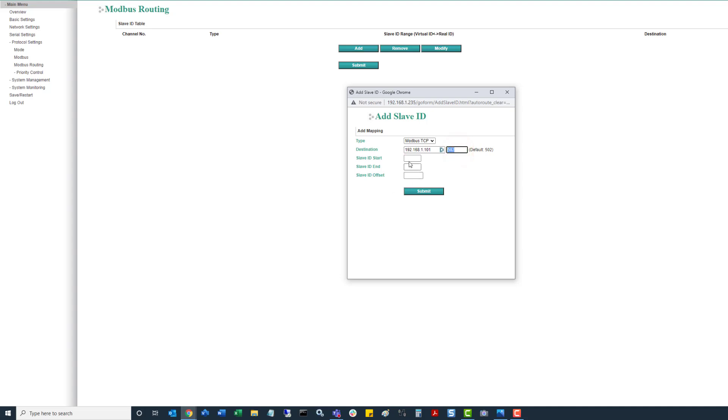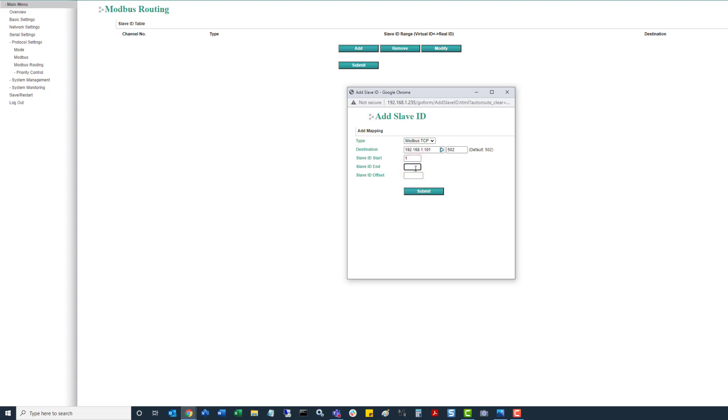So we have a start ID, end ID, and then there's an offset. So on this first one in this example, we're going to be using slave ID 1. So then the end address on this one, because we're doing a one to one bridge, then we'll select end ID 1. And then on the offset, we're just going to leave this at 0. Click on submit.